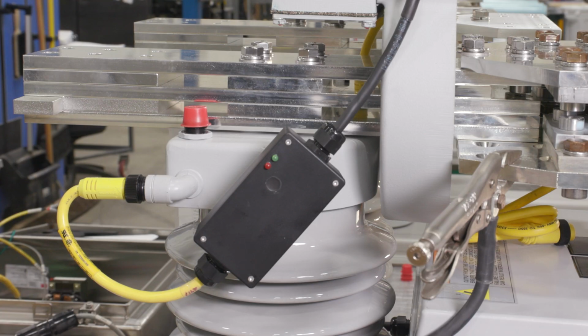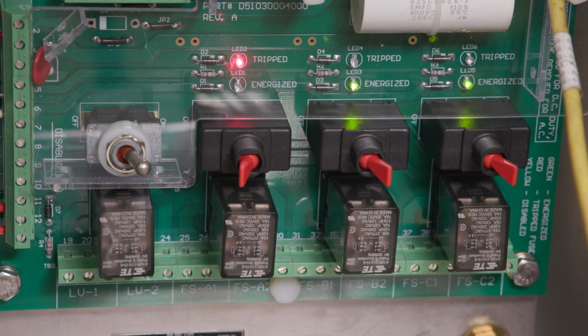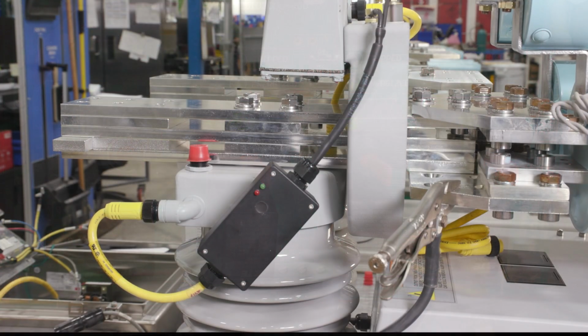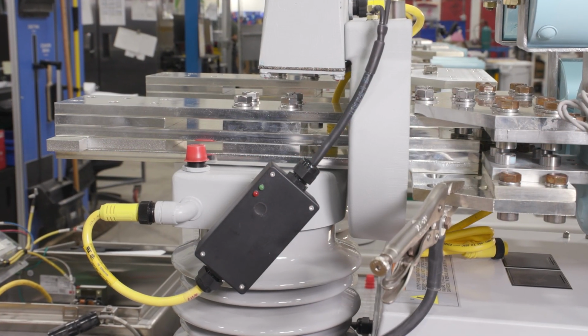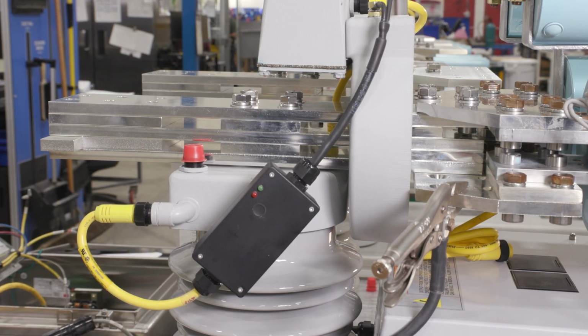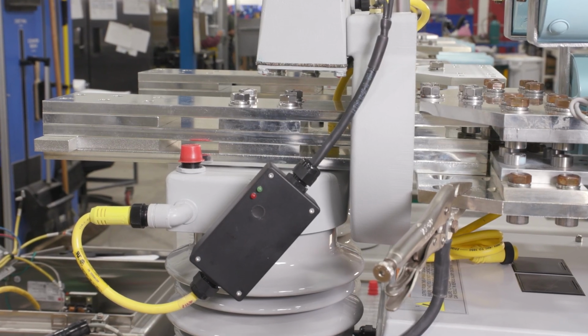The simulator must be reset before resuming tests. This is done by switching the circuit breaker of the trip phase back to the on position. Before resuming tests, wait 60 seconds to allow the simulator to recharge. Then repeat this for all 3 phases.